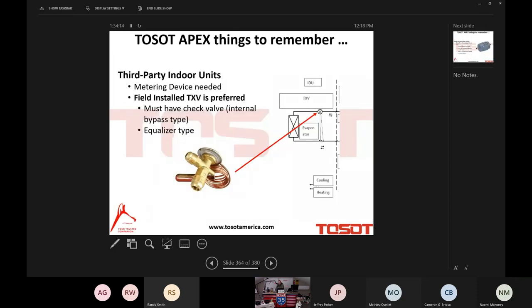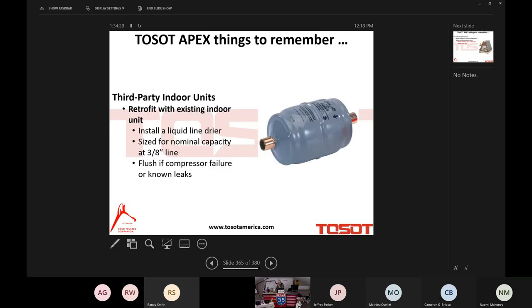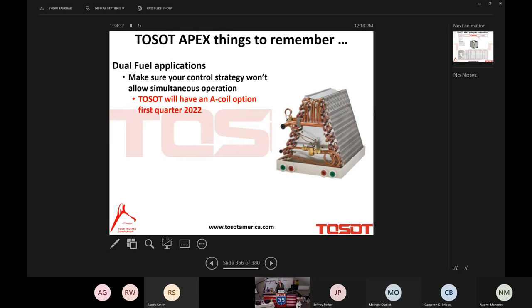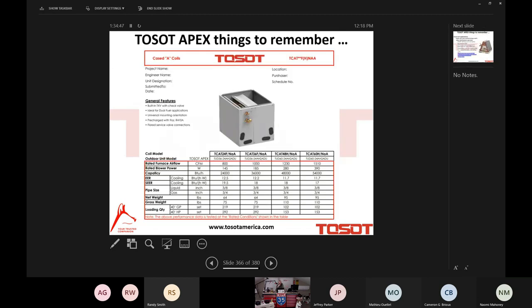As I mentioned to you, if you use a third-party A-coil, which is fine, just make sure it has a TXV. Use a filter dryer and flush the line sets if you're replacing an outdoor unit where there has been a compressor failure. Again, I don't think anything unique about that recommendation. We're going to have an A-coil for you guys, and you know what? We got it. Well, I think we got it, or we're going to have it. There it is. We'll have the four different sizes, four different capacity sizes, just an A-coil. So for your dual fuel applications, which I know is big up there, we will have that product for you. If it's not already in stock, it's on the way, right?